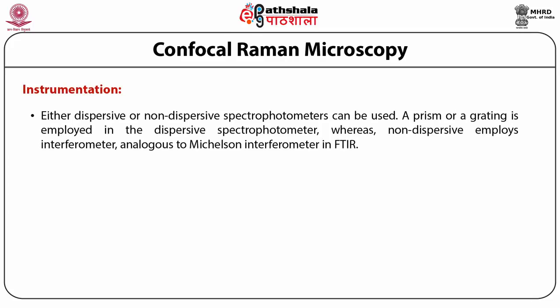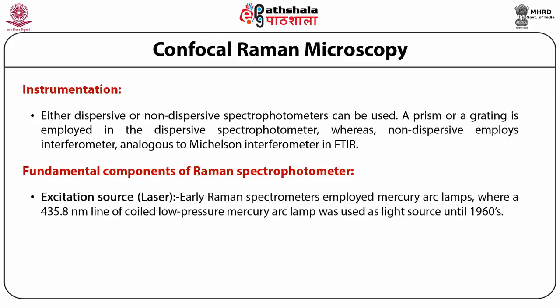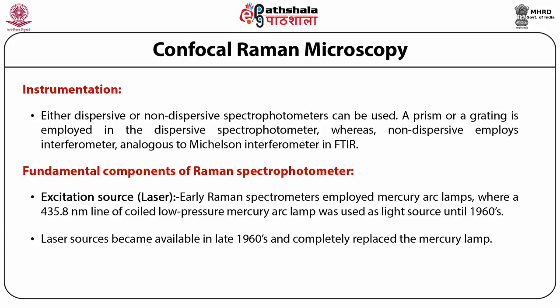Now let us see the instrumentation. Either dispersive or non-dispersive spectrophotometers can be used. A prism or grating is employed in dispersive spectrophotometers, whereas interferometers are used in non-dispersive instruments, analogous to the Michelson interferometer in FTIR. The fundamental components of a Raman spectrophotometer are: first, the excitation source — the laser. Early Raman spectrophotometers employed mercury arc lamps (435.8 nm line) until the 1960s. Laser sources became available in the late 1960s and completely replaced the mercury lamp, providing stable and intense beams of radiation.